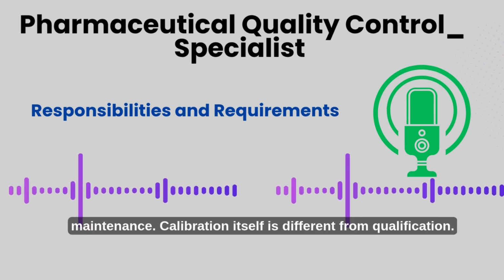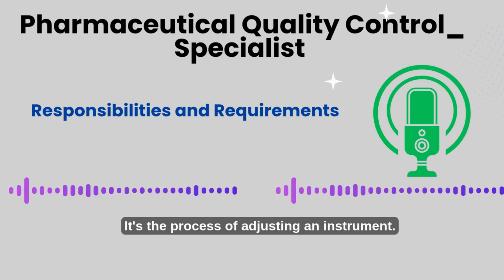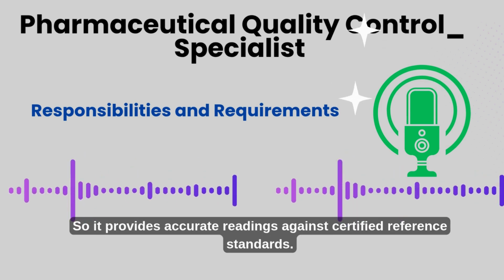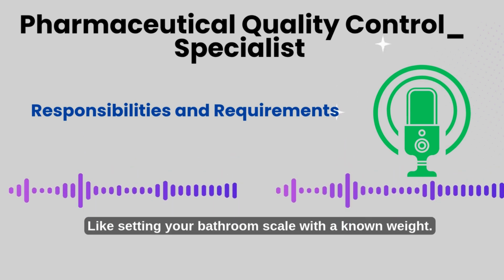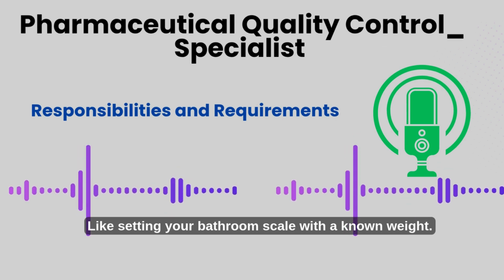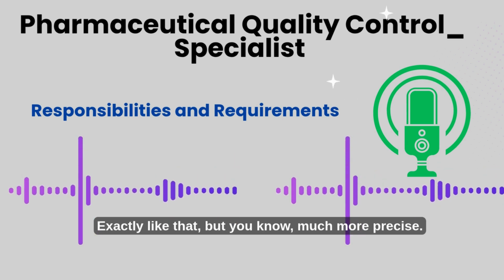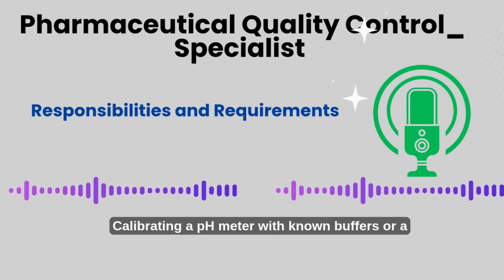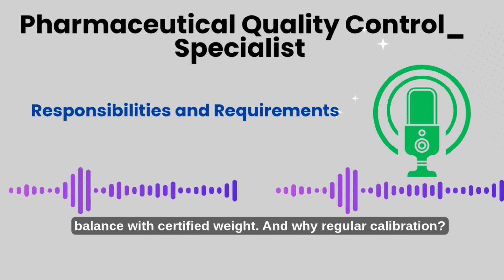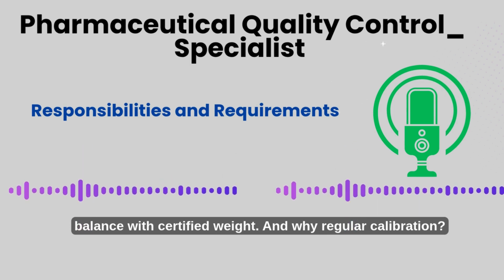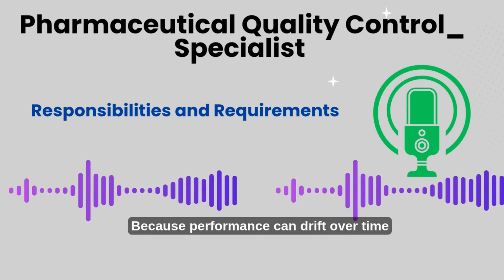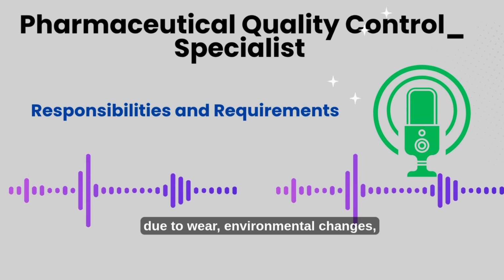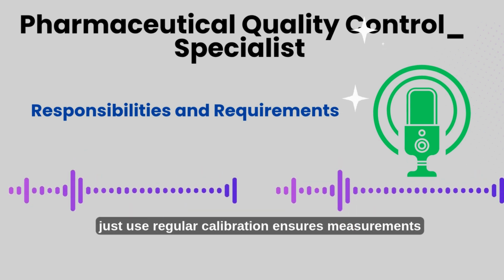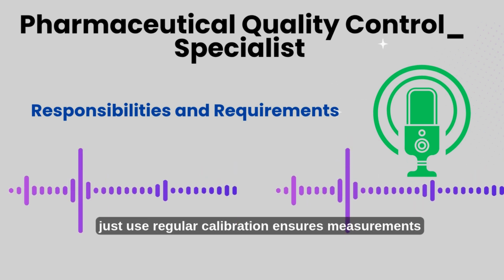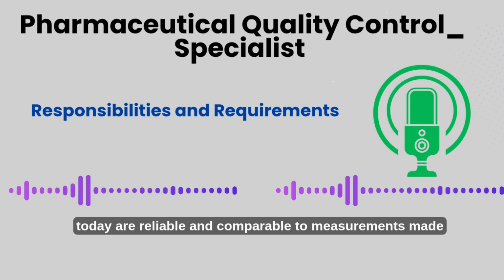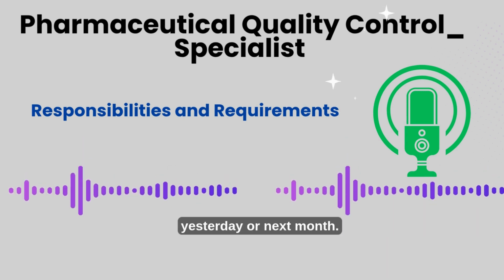Calibration itself is different from qualification. It's the process of adjusting an instrument so it provides accurate readings against certified reference standards. Like setting your bathroom scale with a known weight. Exactly like that, but much more precise. Calibrating a pH meter with known buffers or a balance with certified weights. And why regular calibration? Because performance can drift over time, due to wear, environmental changes, just use. Regular calibration ensures measurements today are reliable and comparable to measurements made yesterday or next month.